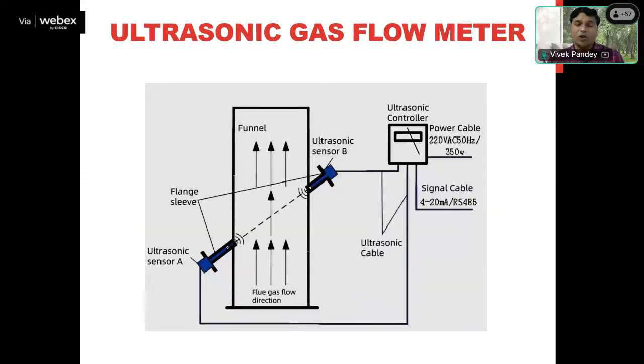When we talk about technologies, as I already mentioned, there are various types of technologies used in the measurement of volume or quantity of gas. Today I am going to speak a little bit about a few technologies which are very commonly used nowadays. One such technology is the ultrasonic gas flow meter, a very useful one where the duct size or pipe size is big. In bigger diameter pipes, these ultrasonic gas flow meters work in a very accurate manner.